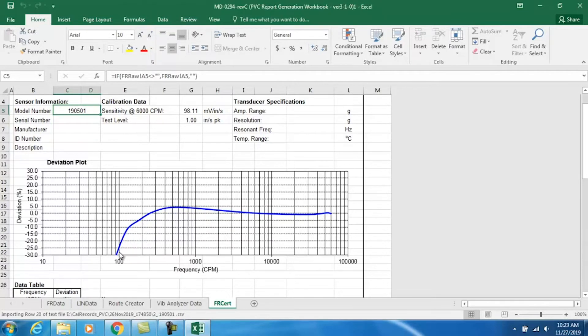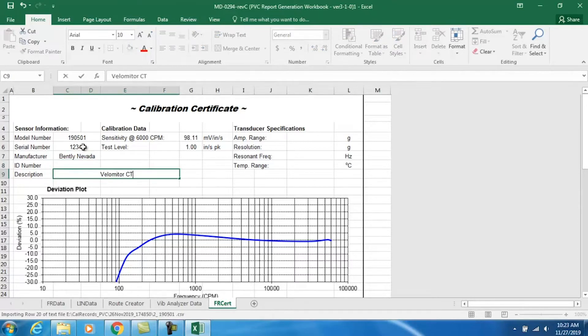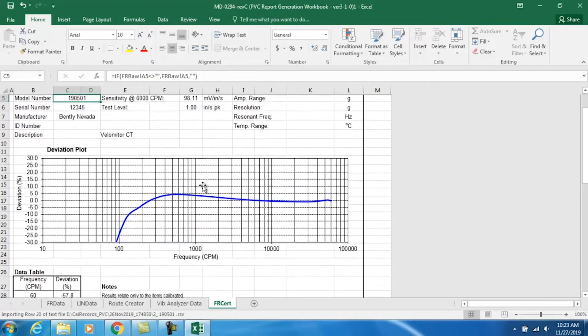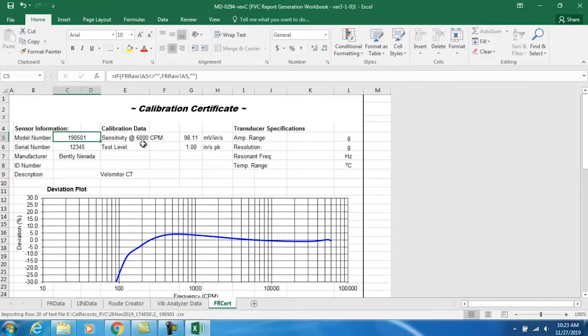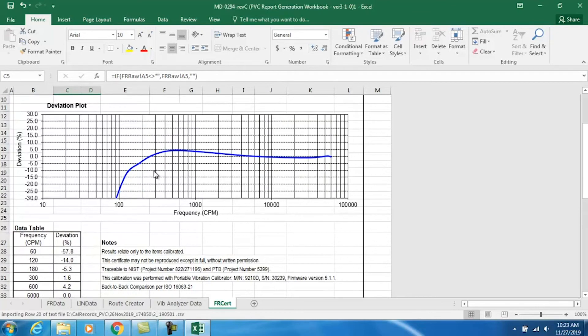You see quite a bit of roll off, which I'll talk about in just a second. To review this sheet, we can enter the serial number, note the manufacturer, and even put a description here for Velomitor CT — all of these cells are adjustable so you can type anything you would like. You can see that the sensitivity at the reference frequency of 6,000 cycles per minute is 98.11 millivolts per inch per second, and our test level at that point was 1 inch per second peak. Scrolling down, you see our deviation plot, which comes from the data in the table.